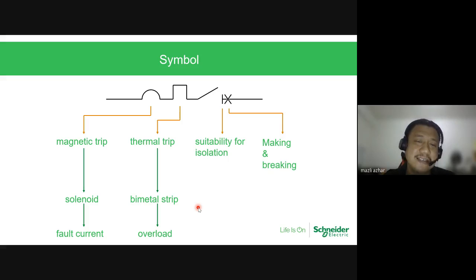So the best is to follow the IEC requirements, so that anyone who knows about this, when they see the design, knows what it is referring to. Each symbol represents something. The semicircle is for the magnetic trip, solenoid for current. The half square, as I call it, is for the thermal trip, bimetal, and overload protection. And this one is for suitability for isolation and making and breaking. When I say making and breaking, it is for the on and off of the power contactor.